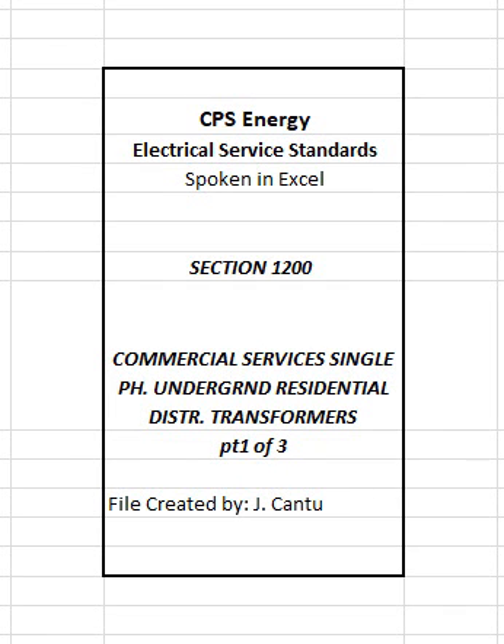Section 1200, Commercial Services from Single-Phase Underground Residential Distribution Pad Mount Transformers. 1201 General. This type of installation typically consists of underground primary voltage cables connected to the electric distribution system and installed in conduit to a CPS Energy-owned single-phase underground residential distribution (URD) pad mount transformer located on customer's premises, public right-of-way, and/or adjacent property. Service is supplied to customer from the pad mount transformer's secondary terminals or secondary enclosure.